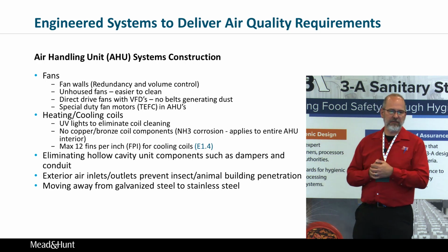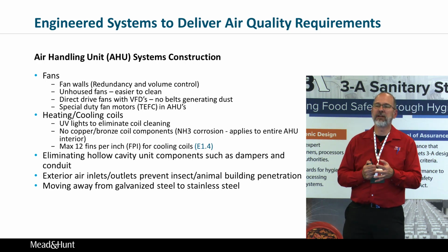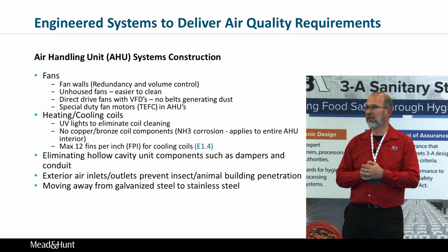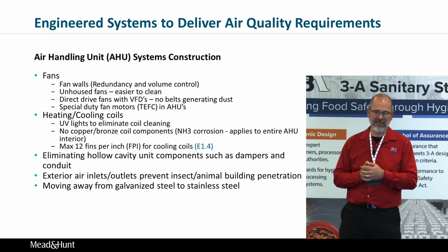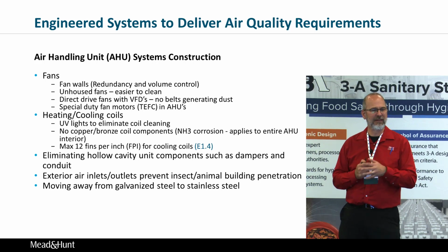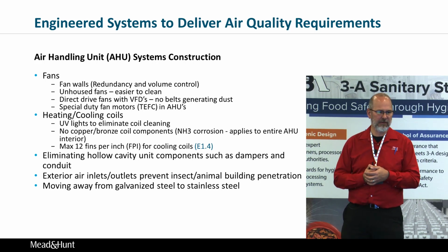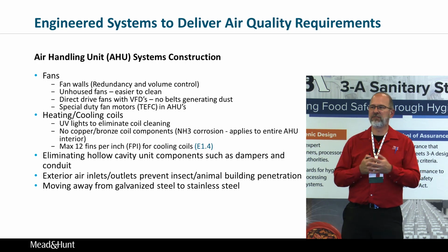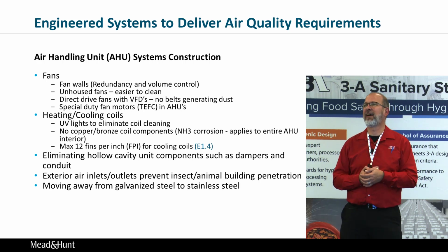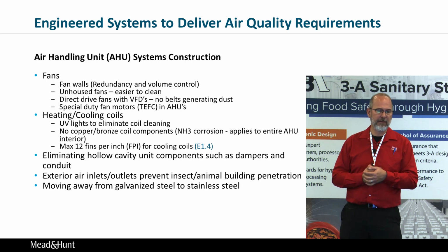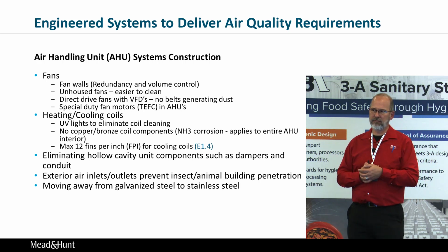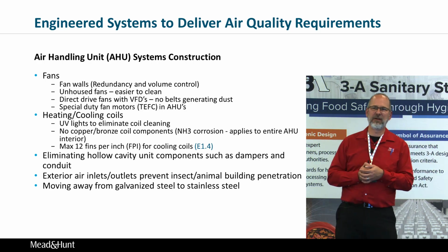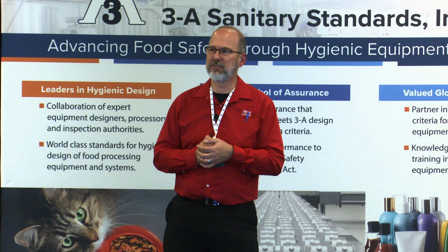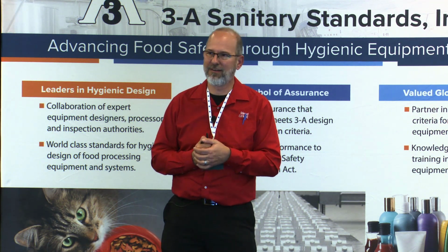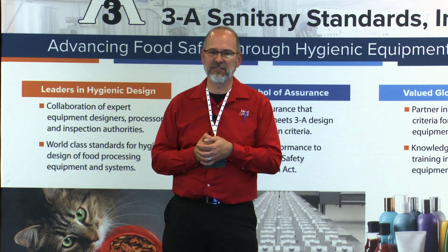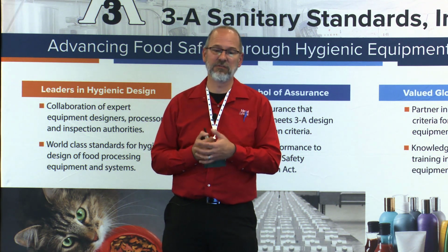So in general, these food-grade units are designed to not have any hollow cavity components in them to the greatest extent possible. It may sometimes be necessary to put a little bit of conduit in the unit, but get all of that outside the unit as much as you can. And again, the unit should be, just like the building, designed to prevent pest penetration. Also in general, the units are going more and more to stainless steel. There still are some elements in an air handler that aren't stainless steel, just because HVAC OEM manufacturers don't make a lot of it in stainless steel yet. It's hard to get stainless steel fans in these units. They're really pricey. Usually they're epoxy coated steel.